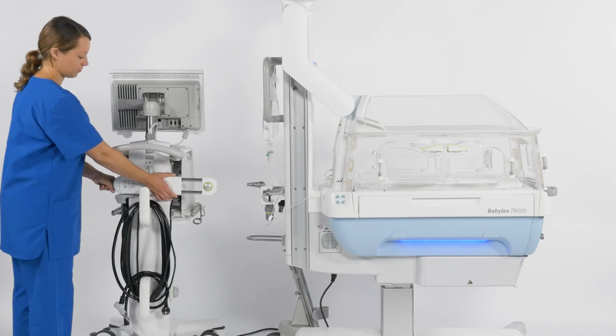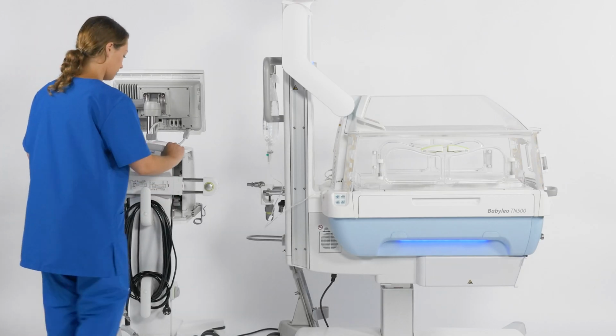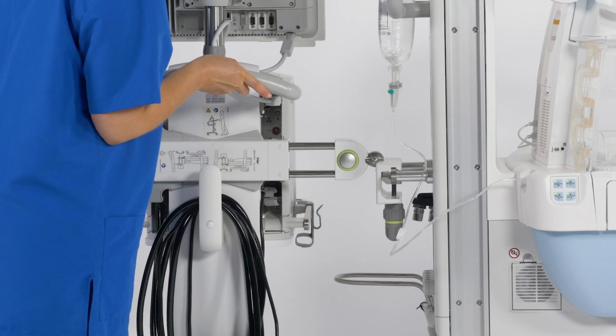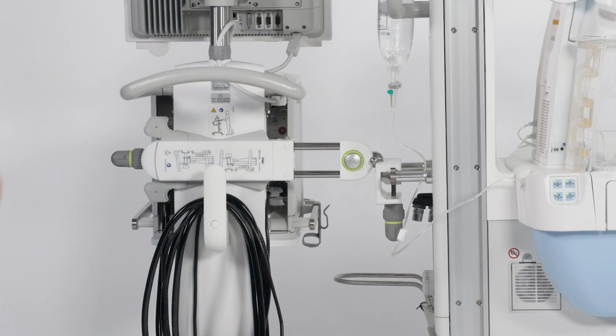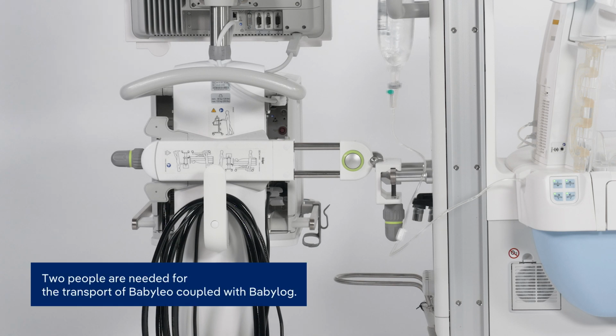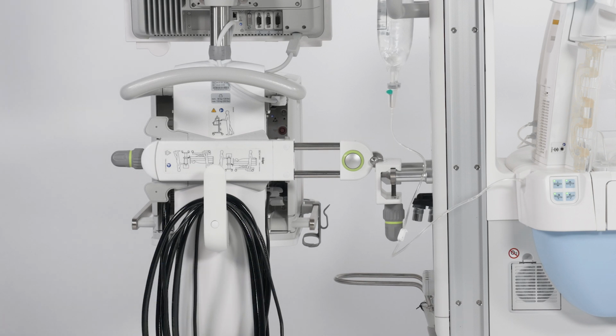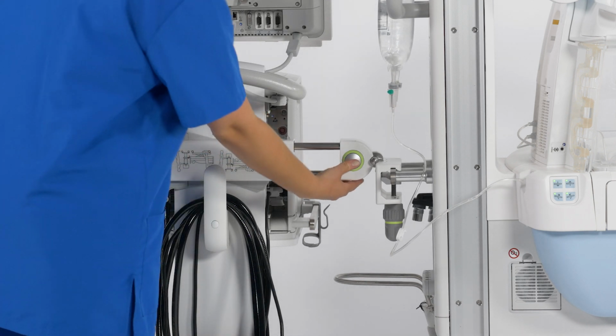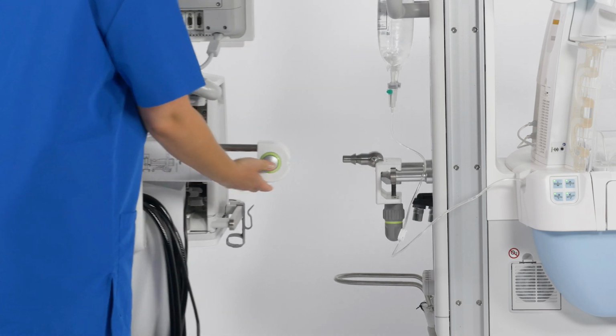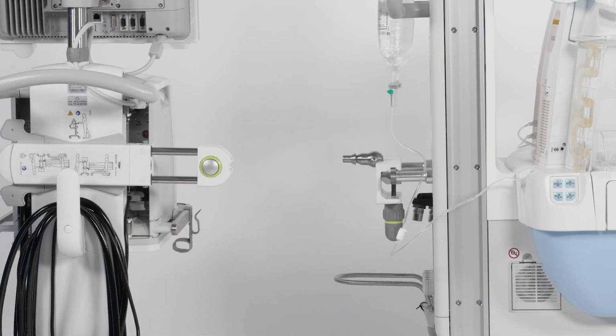Then connect the device side coupling with the bedside coupling by moving the Babylog towards the Babyleo until the bed coupling clicks into position. Adjust the distance between Babylog and Babyleo if needed. Transport should be performed with a minimum of 2 people while constantly monitoring the patient's condition. To disconnect, press the button and move Babylog away from Babyleo. After transport, plug in the mains power cable, switch on Babyleo, and check the therapy settings.